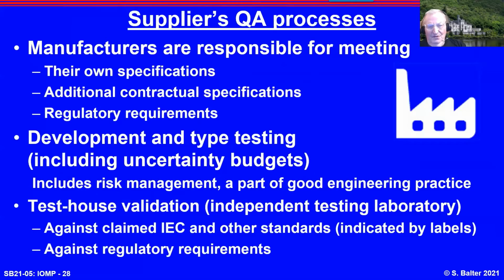Manufacturers do their best to deliver equipment that performs properly, that meets specifications. They treat this very seriously. They have elaborate systems to do this. Part of the process, as they develop equipment and do the type testing, they do uncertainty budgets. In the manufacturer's world, this is called risk management. They maintain careful files which the regulators inspect to see whether the risks are adequately managed.